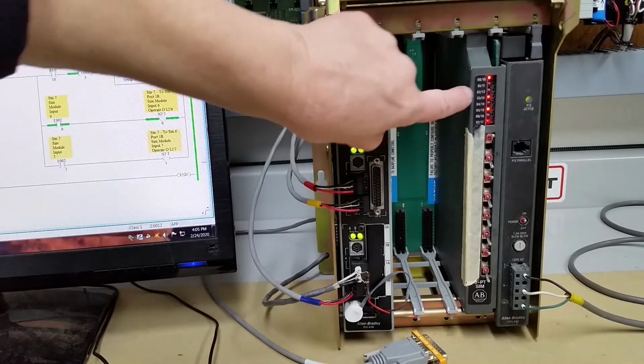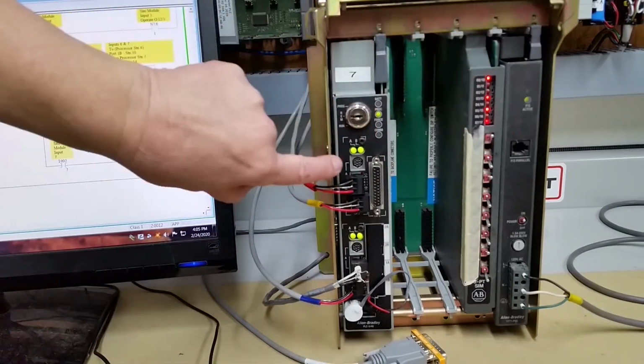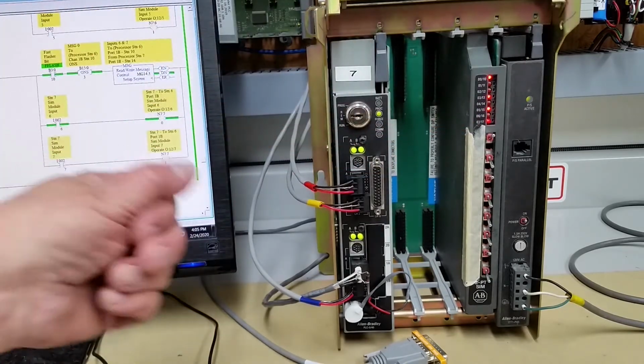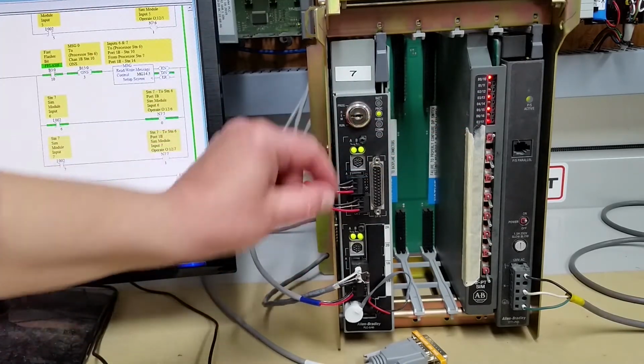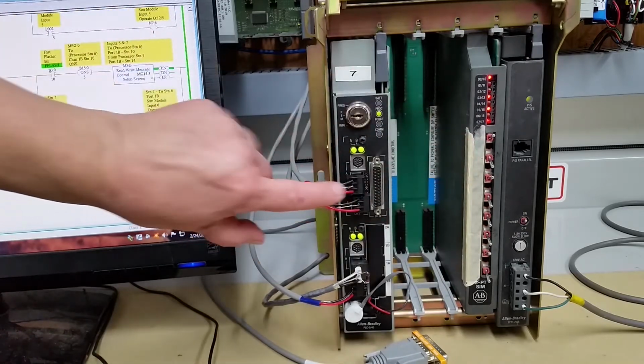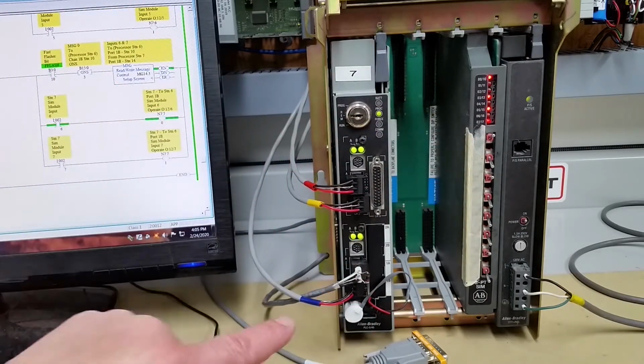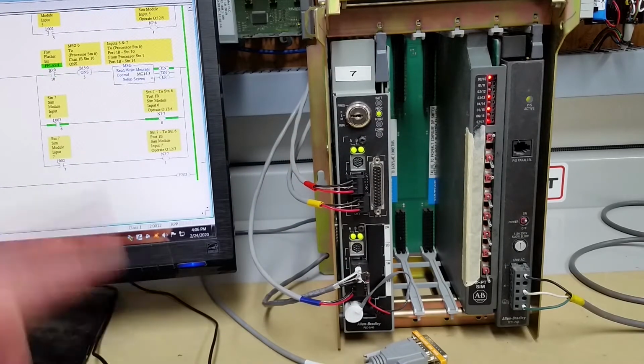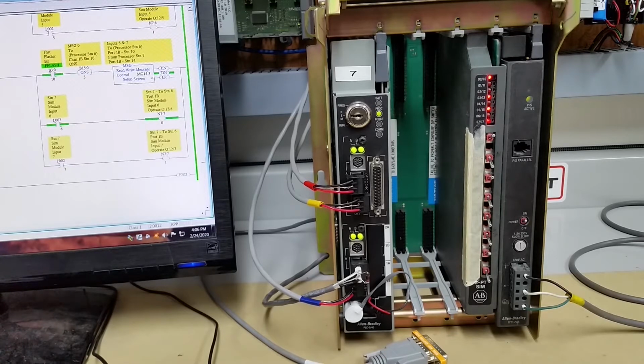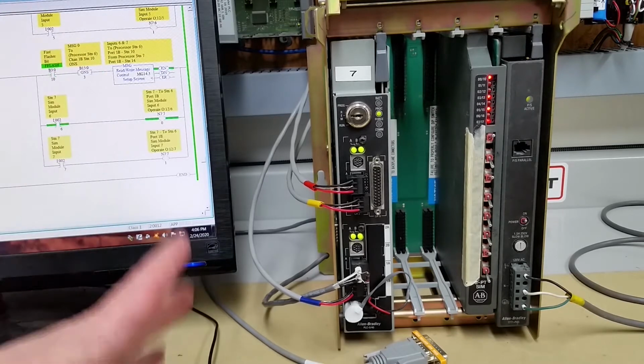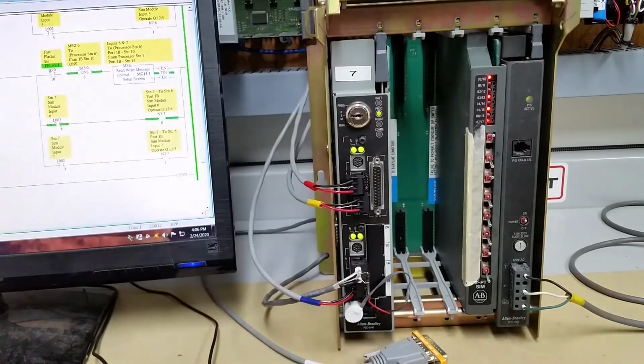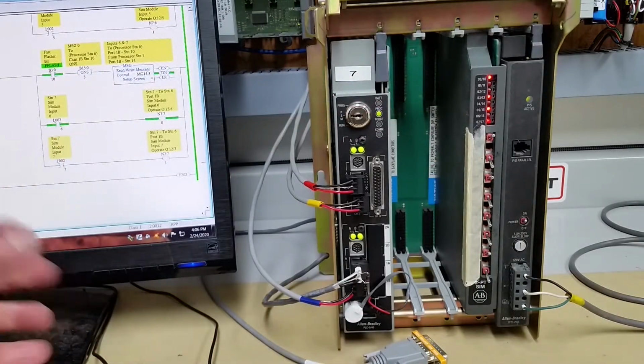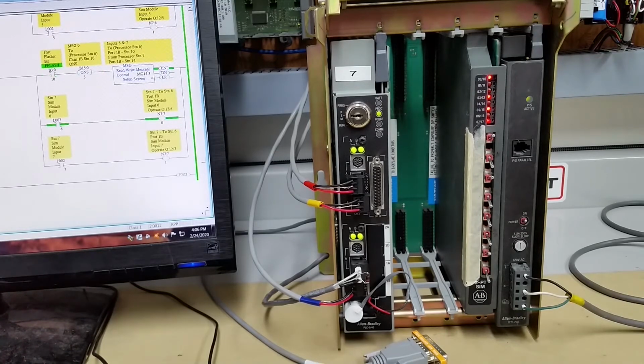What this proves, because the way I've programmed it is 2 switches, 2 lights, 1 channel, back and forth between station 6 and 7, is that all of the ports have bidirectional communications in them and they all work properly. That way you know, like I say, you put a label on your processor, put it on the shelf in your box, and you know that that thing is good.